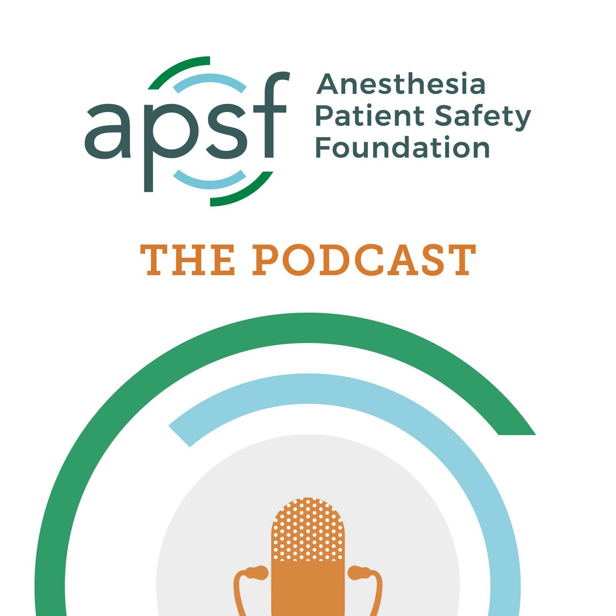First, what does this alarm detect? This alarm signals when the pressure in the breathing system does not meet a minimum threshold pressure in a certain amount of time, or very simply, when there is a loss of pressure in the breathing system. The low-pressure alarm may detect circuit disconnections, leaks, accidental extubation, fresh gas flow system failures, ventilator setting errors, obstructions within the anesthesia machine, and problems with the scavenging system. This is a pretty long list that anesthesia professionals may need to troubleshoot. Don't worry, we will go into more detail later.